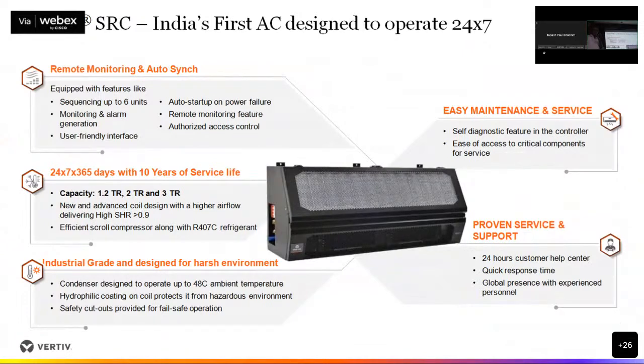The line interactive UPS inverters are designed only for standby application, whereas this is designed for 24/7 operation. It comes with a remote Modbus protocol where you can monitor remotely. And third, it can be scaled up to 6 machines. If you are growing over a period in a small room and your load is increasing, you can still increase the capacity.